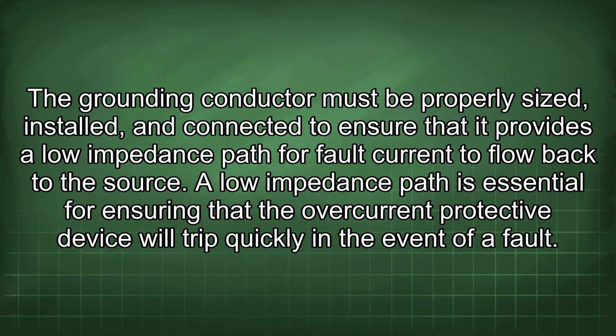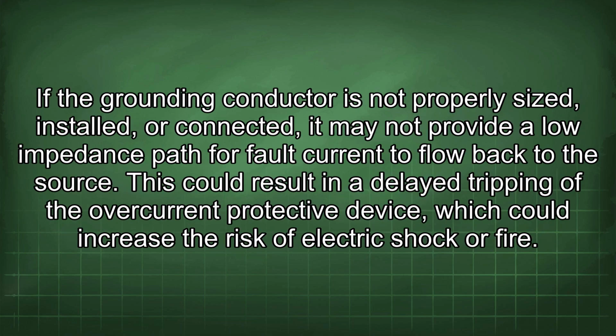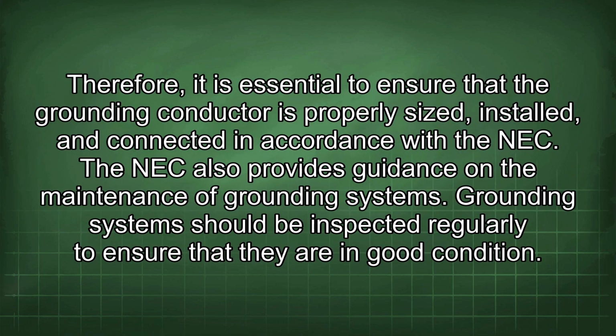A low impedance path is essential for ensuring that the overcurrent protective device will trip quickly in the event of a fault. If the grounding conductor is not properly sized, installed, or connected, it may not provide a low impedance path for fault current to flow back to the source. This could result in a delayed tripping of the overcurrent protective device, which could increase the risk of electric shock or fire.